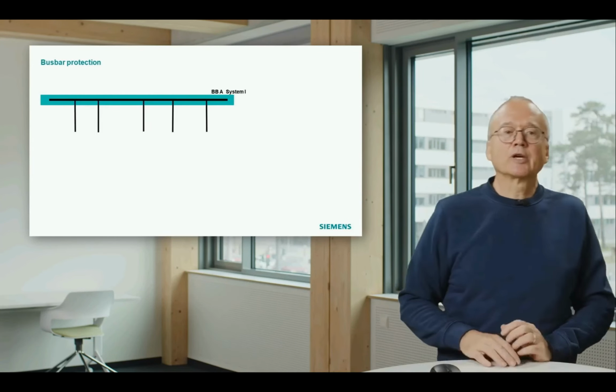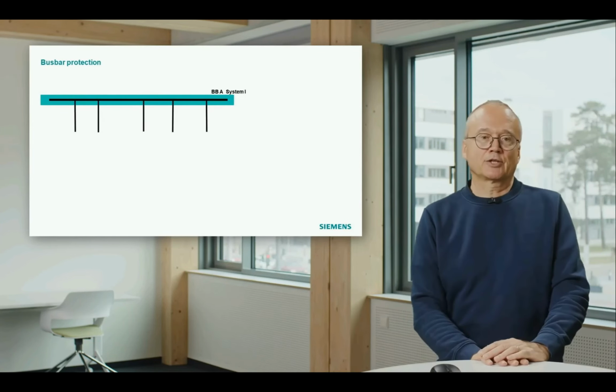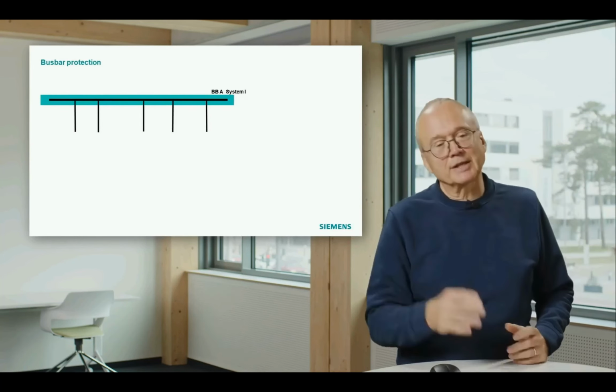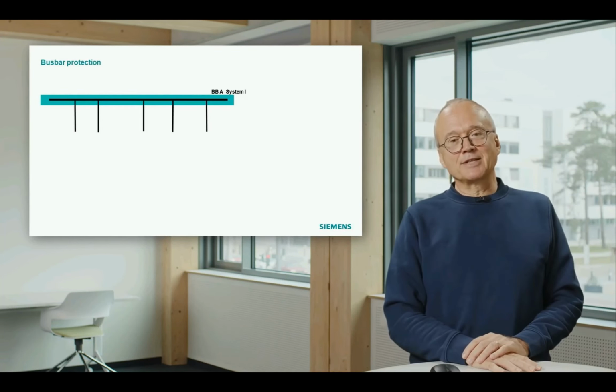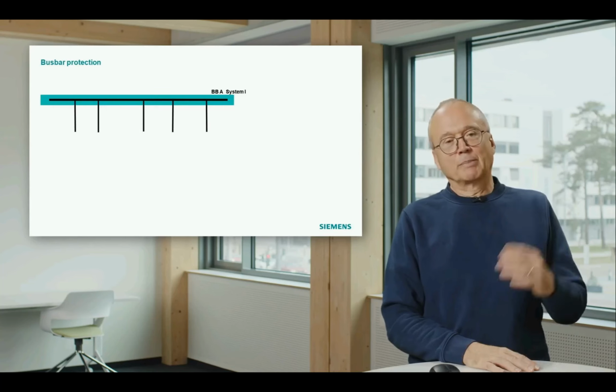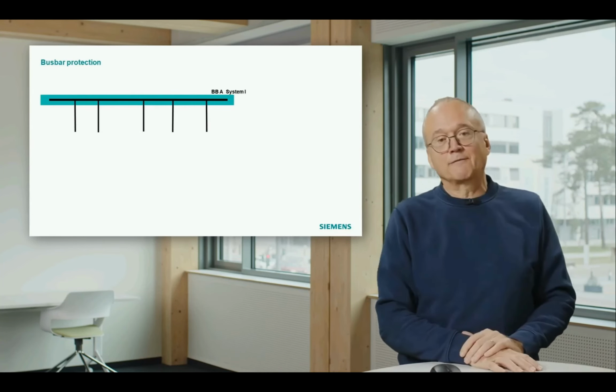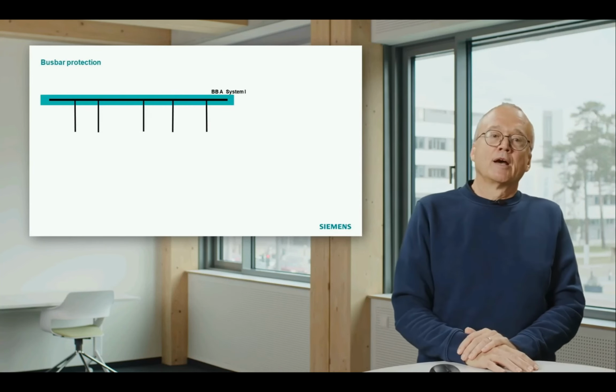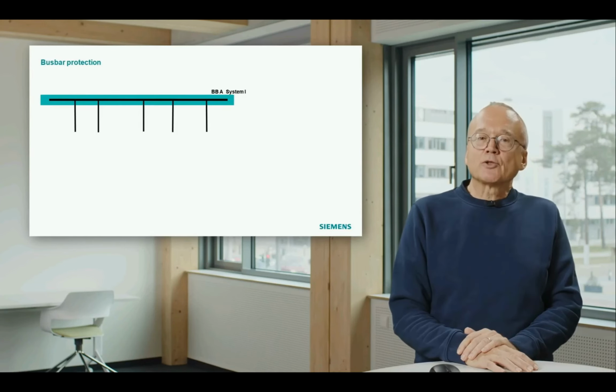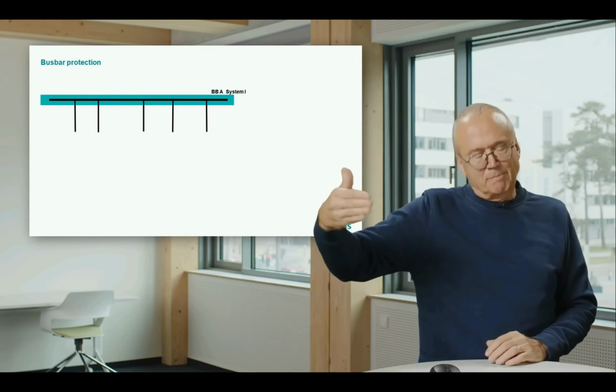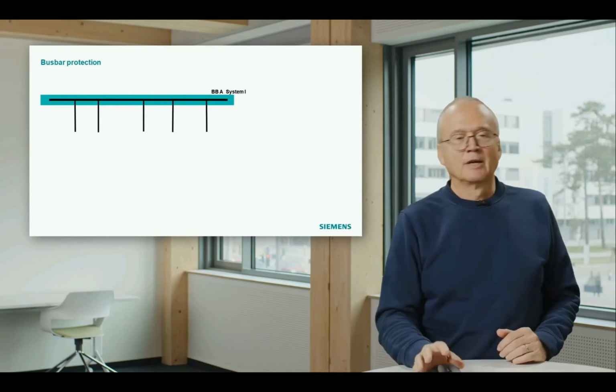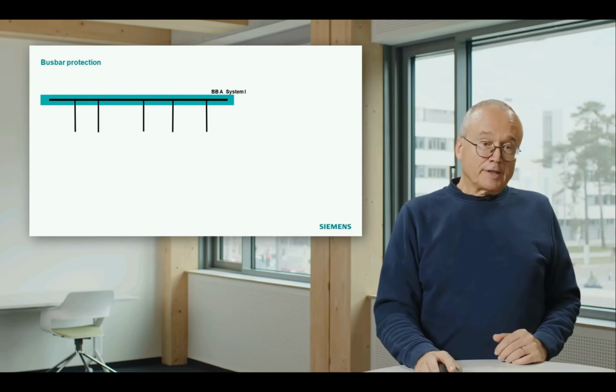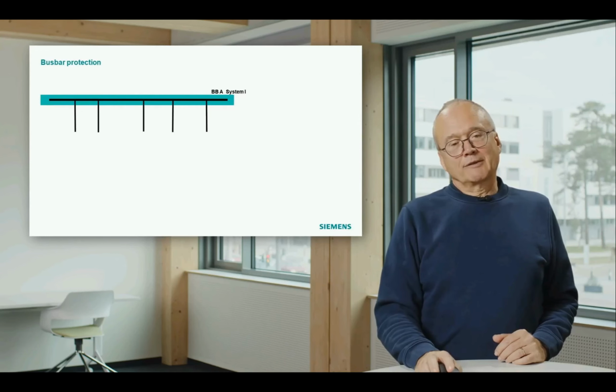And the third area of application is the busbar protection. Busbar protection, it looks pretty easy. Well, we have a busbar, we have in this case 5 outgoing feeders, and we just measure the currents and sum that up. Always separately for the 3 phases. Often these substations don't unfortunately look that easy.